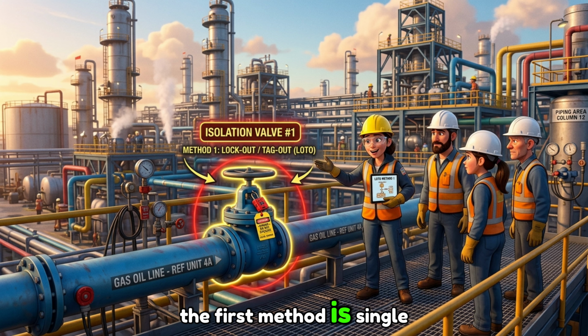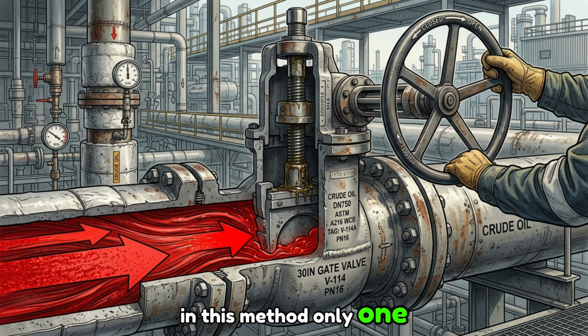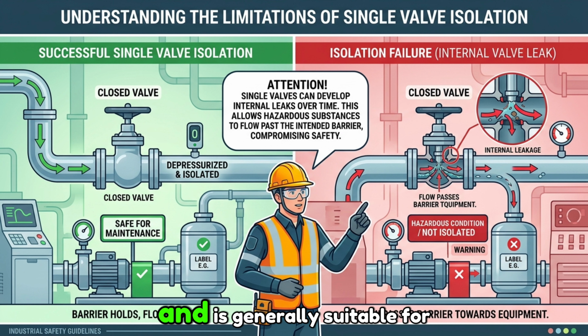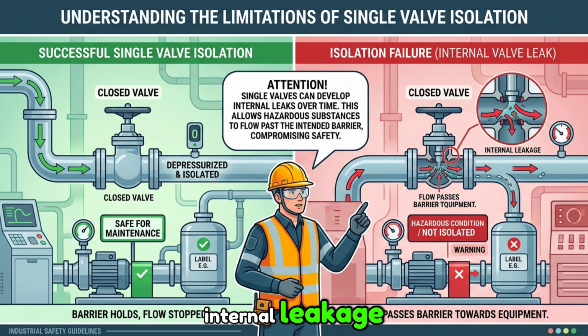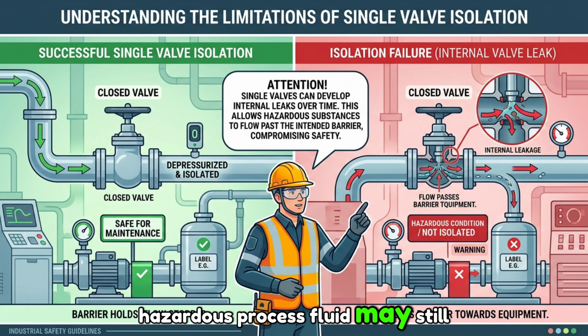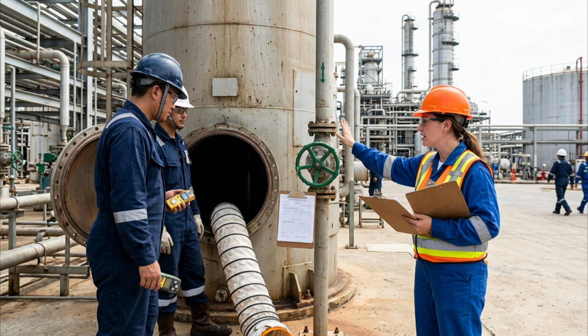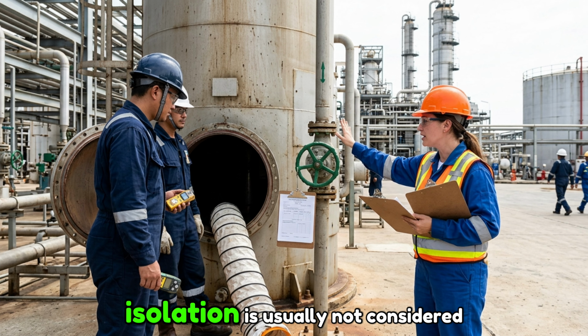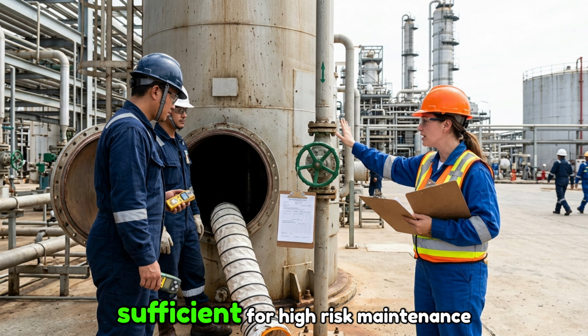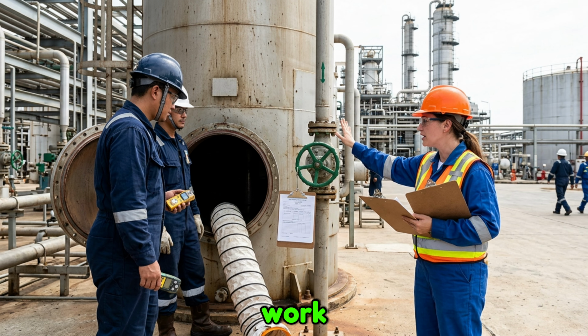The first method is single block isolation. In this method, only one isolation valve is closed to stop the process flow. This is the simplest isolation method and is generally suitable for low-risk activities. However, if that valve develops internal leakage, hazardous process fluid may still reach the equipment. For this reason, single block isolation is usually not considered sufficient for high-risk maintenance work.